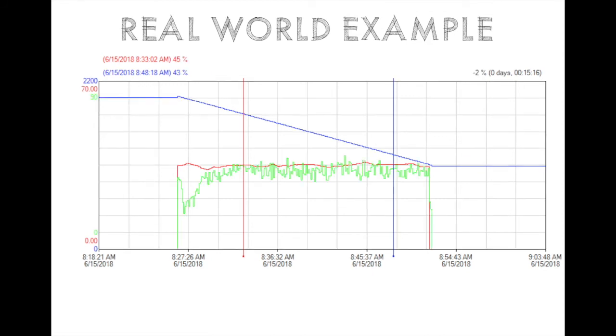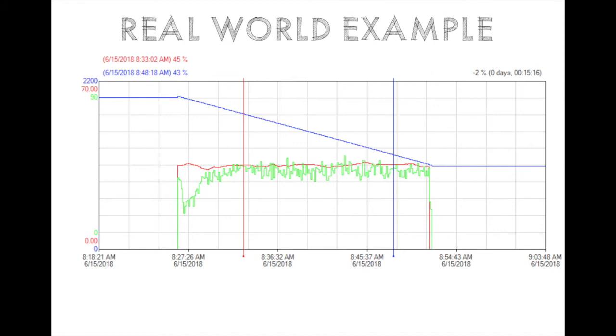So this is what it looks like when everything is going well. Now the green here I'm showing is the screw speed. It's the percent output of the motor. So 100% being the hardest that the motor can work and zero being the motor is off. So we saw the theory that as the hopper gets lower, the screw speed should be increasing because there's less of a head pressure caused by the powder. We don't actually see that, but it is fairly constant in this case.